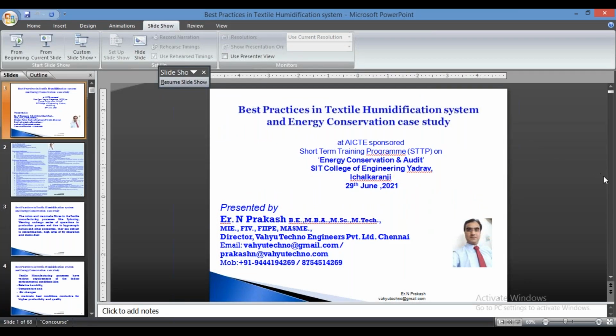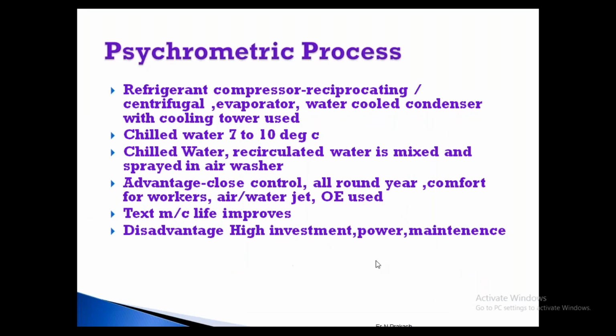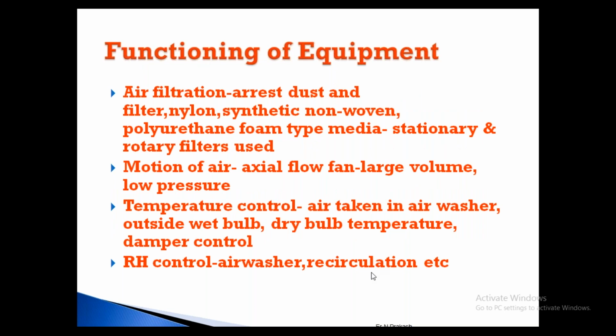So if I explain the functioning of the equipment, whatever dust is generated has to be filtered first. That is our requirement in the production process. There will be a lot of dust accumulated, floating fluff, and fly liberation, and that has to be filtered. So the provision should be there in our air conditioning station. For that we have an air filtration arrangement. It will arrest the dust, and different types of filters are used.